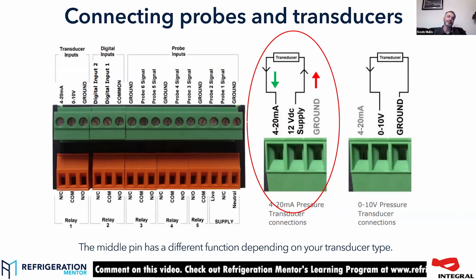As I say, you can connect it directly to the controller. There's also, if you use an RDM communication hub, you can wire a transducer into that, and then everything that's on the controller side of that hub can receive that pressure reading. You can also, as I said earlier, if you don't want to do that and you don't want to fit the controller with the transducer, broadcast the reading off of the rack controller. All you've got to do is tick a box in the setup to say broadcast, and you can configure the controller to read that off of the network. Obviously, there's benefits and pitfalls to both. If you lose network and you're broadcasting the transducer reading, you will lose the transducer reading, but it's potentially considerably cheaper than installing like 50 transducers. So it depends on your setup. It depends how much resilience you want.